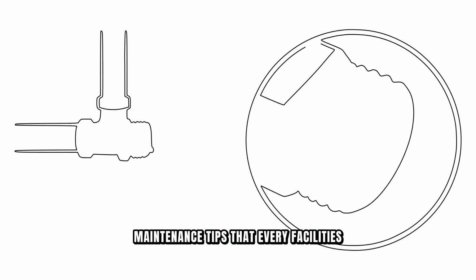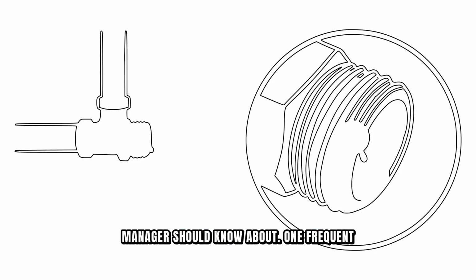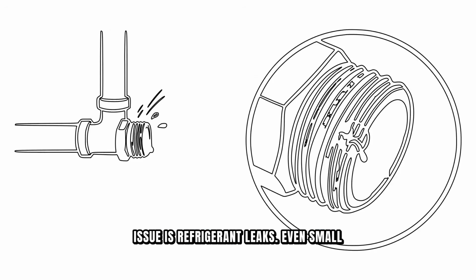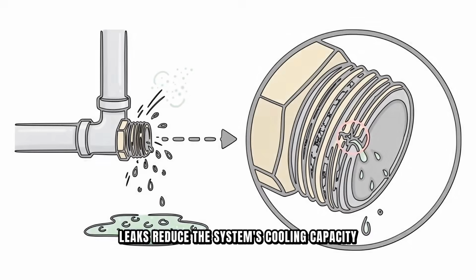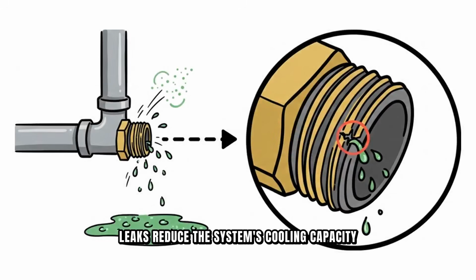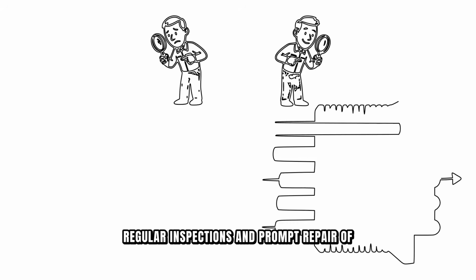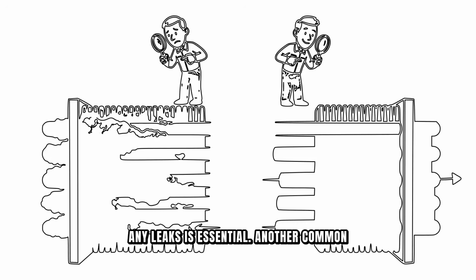Let me share some common problems and maintenance tips that every facilities manager should know about. One frequent issue is refrigerant leaks. Even small leaks reduce the system's cooling capacity and can eventually damage the compressor if the system runs low on refrigerant. Regular inspections and prompt repair of any leaks is essential.